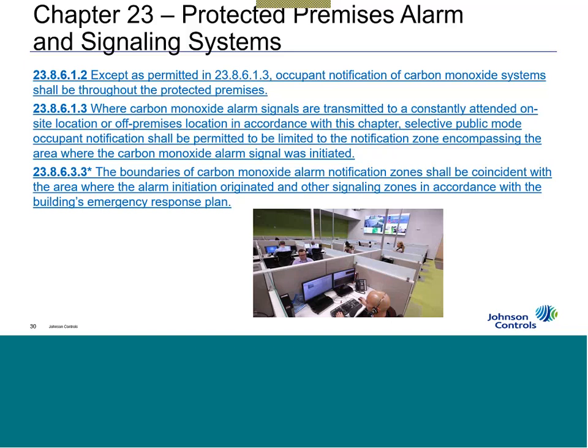So if I'm at a constantly attended location monitoring the system and/or I'm sending it off to a supervising station, I've only got to make the temporal 4 signal activate at minimum where the carbon monoxide detector activated. So this is the confusion that people start to get. Well, I got to go them everywhere. No, you only need it in one area. Now remember, this is a minimum requirement. So the code says at minimum you have to do the area. So if you say, well, gee, I want to do the whole floor or floor above, floor below, that's fine. If it's monitored on-site or off-site, you can do that. If it's not monitored at all, you've got to send the signal everywhere.